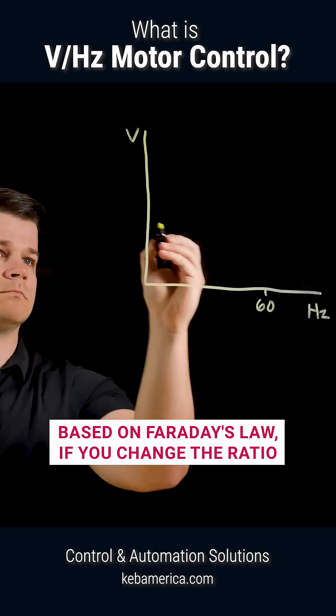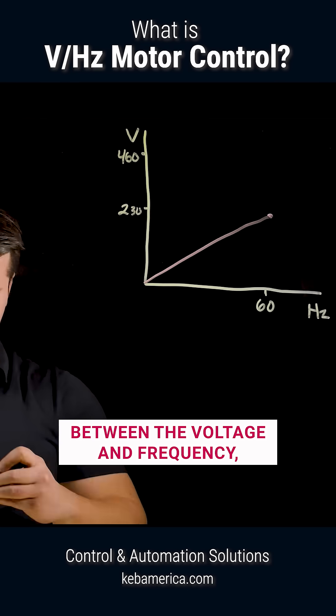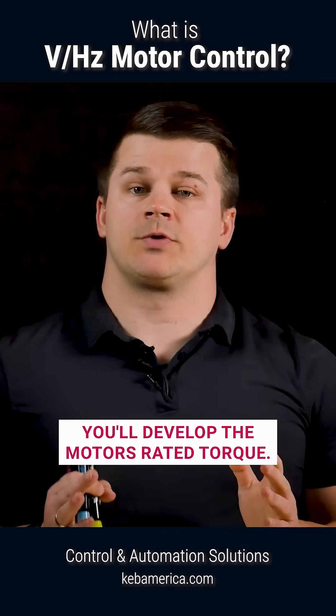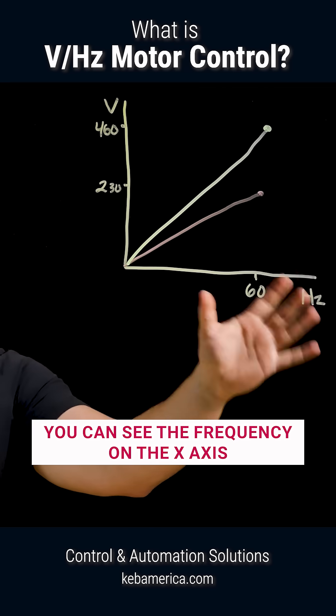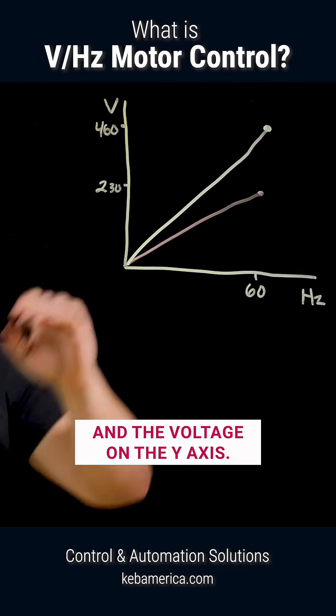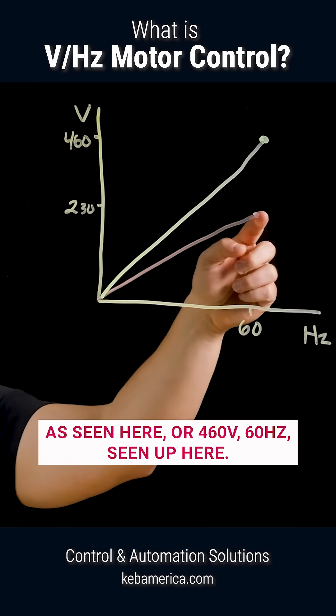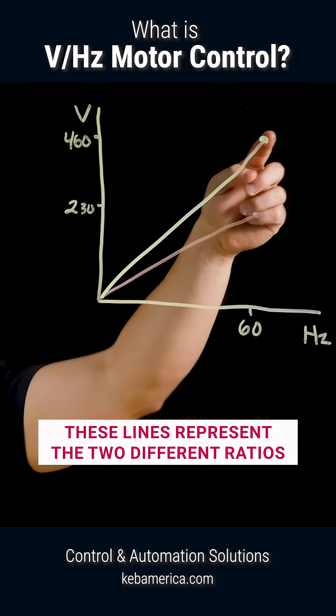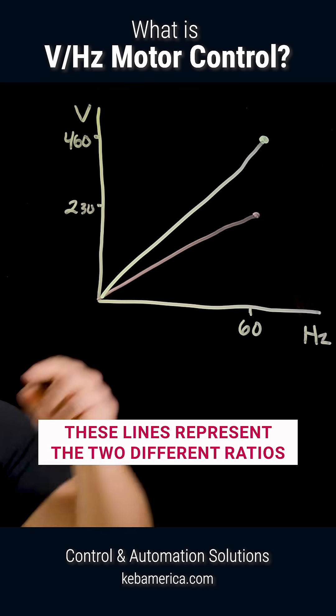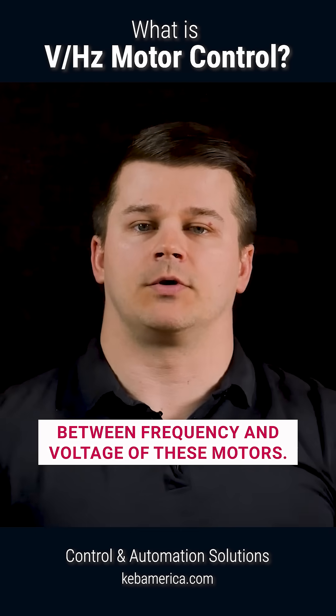Based on Faraday's law, if you maintain the ratio between the voltage and frequency, you'll develop the motor's rated torque. In this graph, you can see the frequency on the x-axis and the voltage on the y-axis. A common U.S. winding will be 230-60 Hz, as seen here, or 460-60 Hz, seen up here. These lines represent the two different ratios between frequency and voltage of these motors.